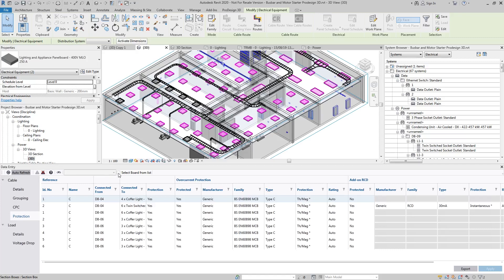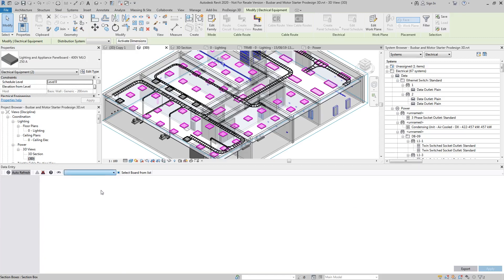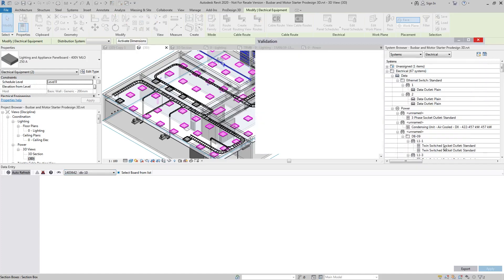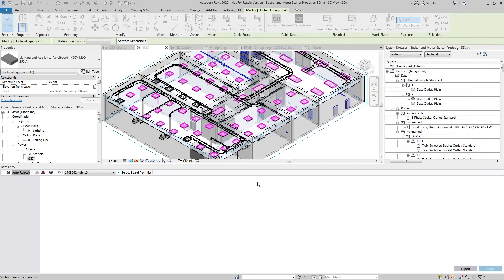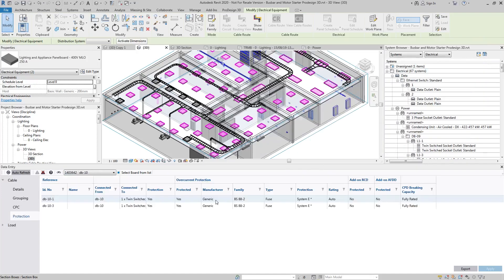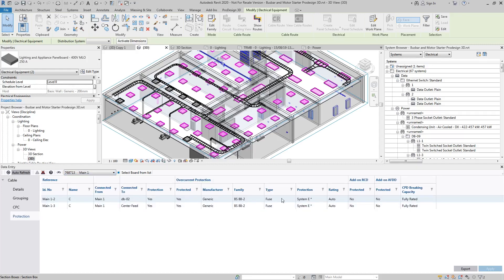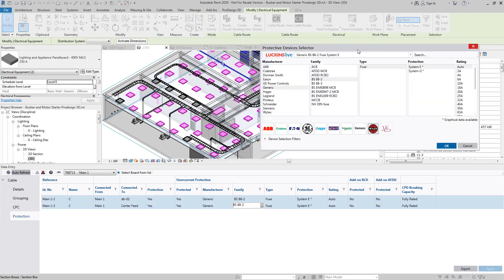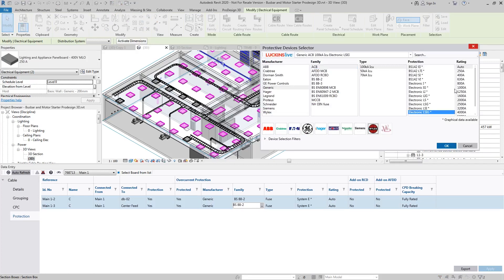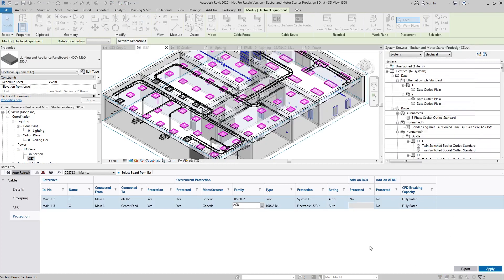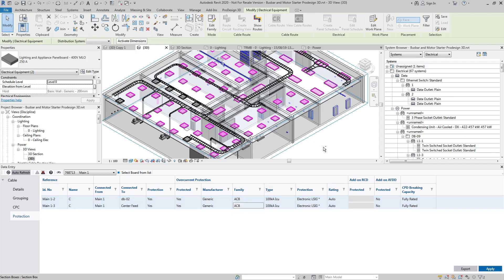If you wanted to do this on a board level, so you only want to work on certain boards, you click this button here, then select that item and go right, I want to work on DB10. I've got some mismatching items—that's not really a problem—but I can change that. Just to show that again, I could say I want to work on the main board. I select the main board, I can then go right, okay, these items—well actually I don't want these to be BS88-2 fuses, I want them to be ACBs and I want them to be LSGs. Click that through, okay, I want to make those changes, and then all the changes are applied within the model.